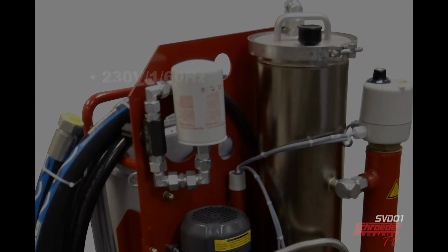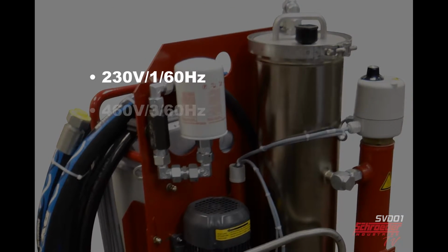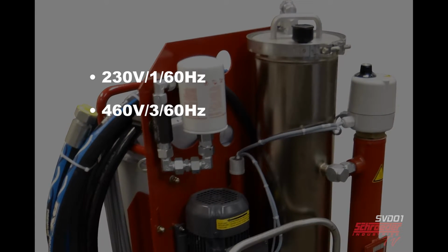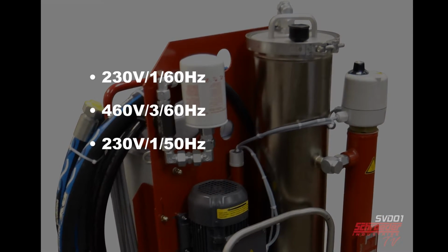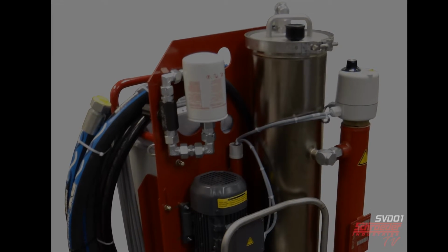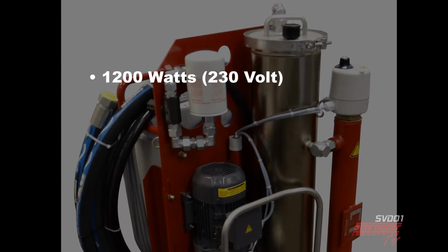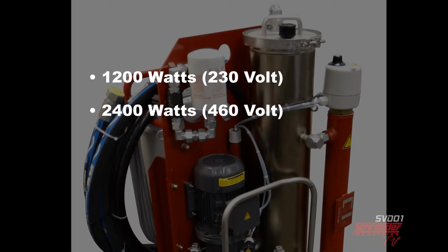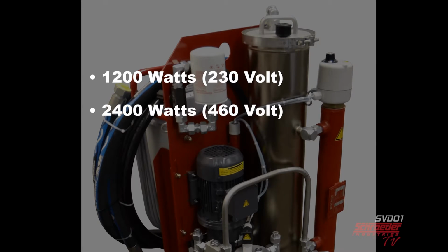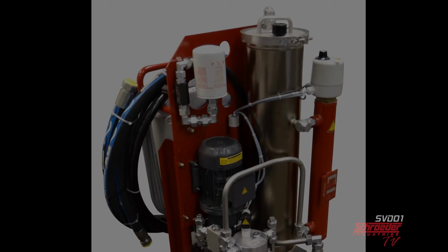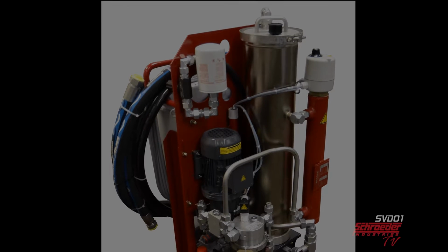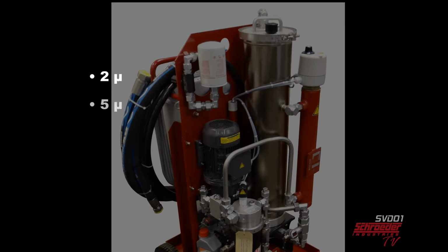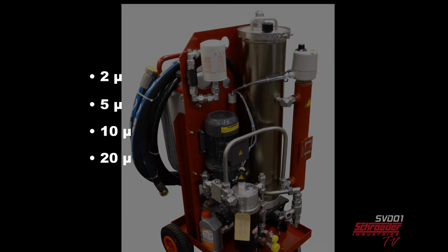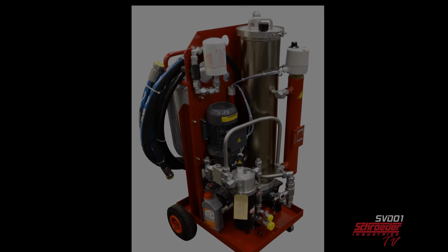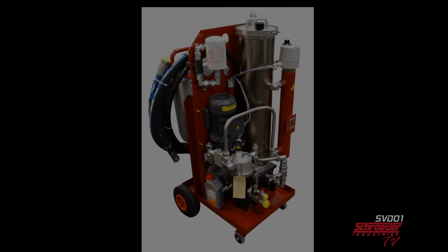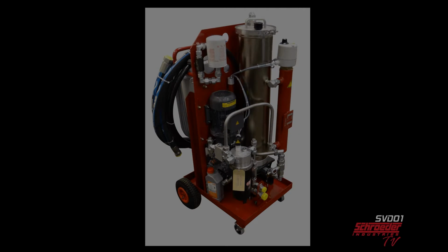Our voltage options consist of 230-volt single-phase 60 Hz, 460-volt 3-phase 60 Hz, and 230-volt single-phase 50 Hz. There are 2 power option sources, 1200 watts for the 230 volt and 2400 watts with the heater for the 460 volt versions. The SVD01 vacuum dehydrator comes equipped with 4 different media selections: 2 micron, 5 micron, 10 micron, and 20 micron. You can, but you are not required to, include a contamination sensor and/or water sensor with your SVD01.